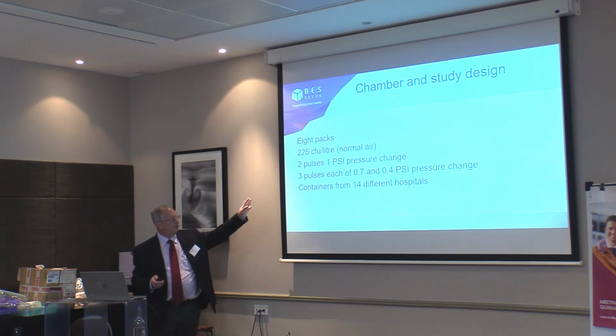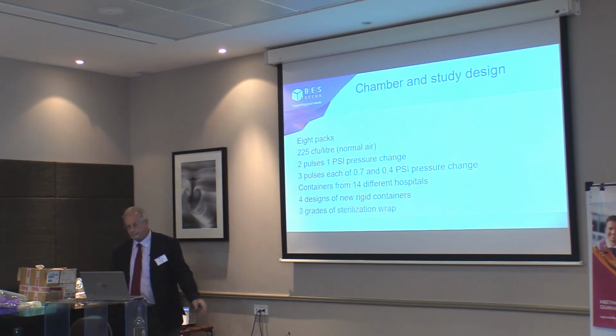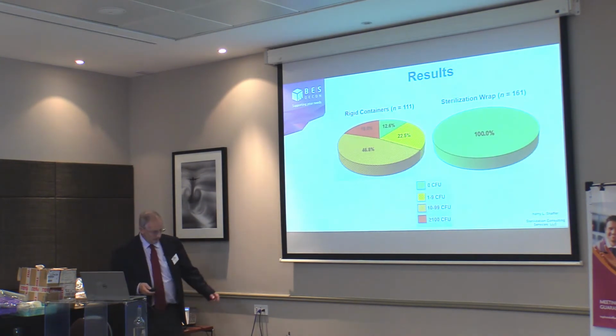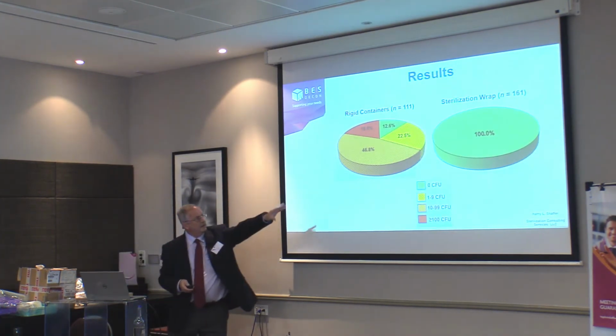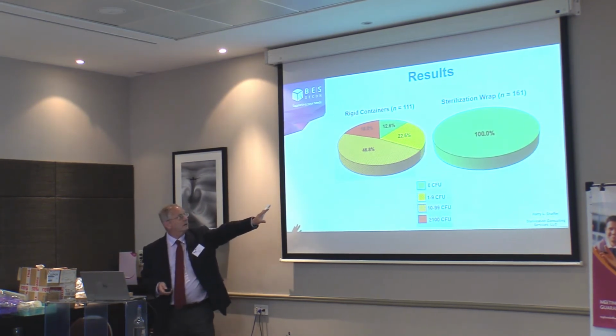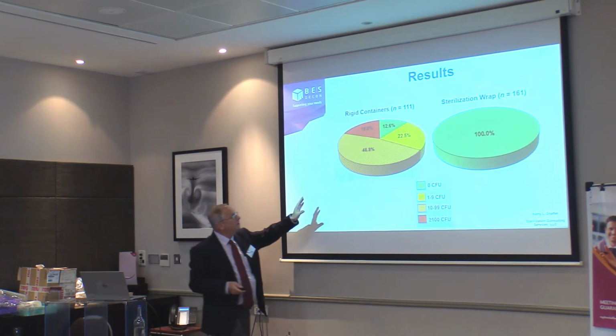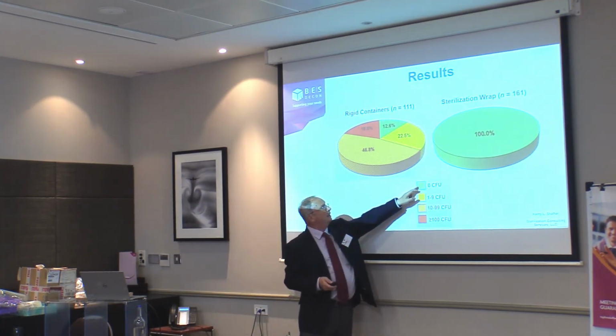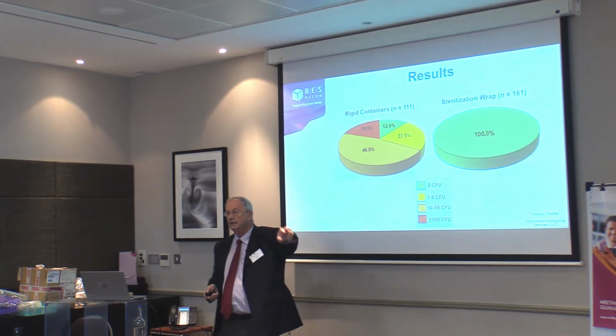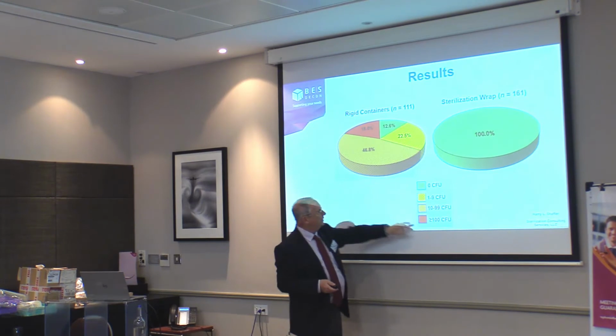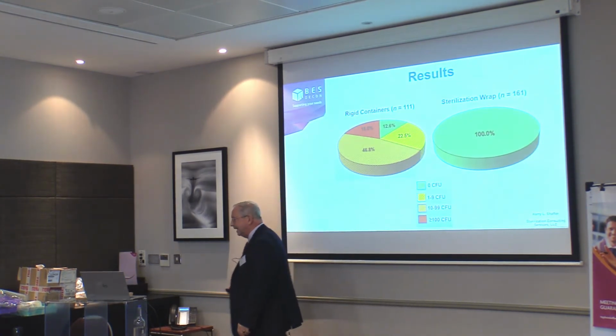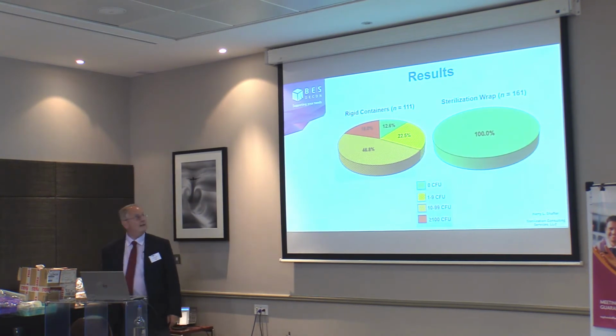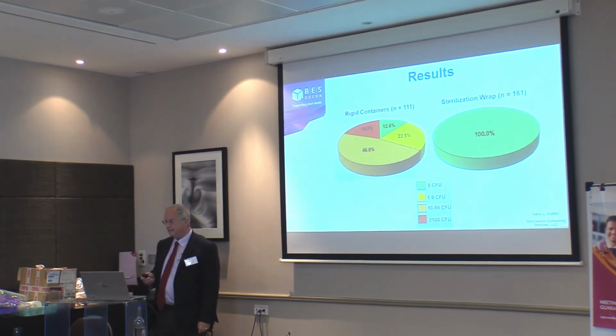They looked at 14 different hospitals, containers from there, and they used 4 designs of new rigid containers. And as I said a moment ago, 3 grades of sterilization wrap. Putting all those items through that test rig, 100% of the sterilization wrap ones, there were no bacteria came inside. Of the rigid containers, only 13% had no bugs inside at all. 18% had over 100 CFU. That is a heck of a lot of contamination. These include brand new rigid containers.